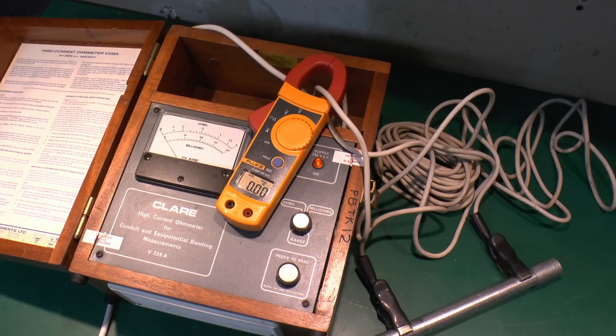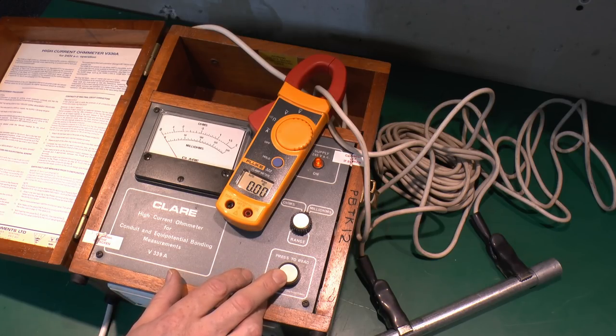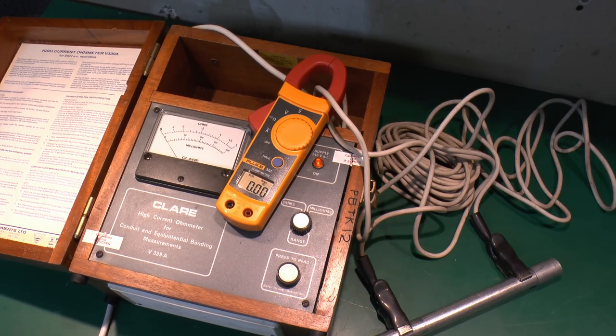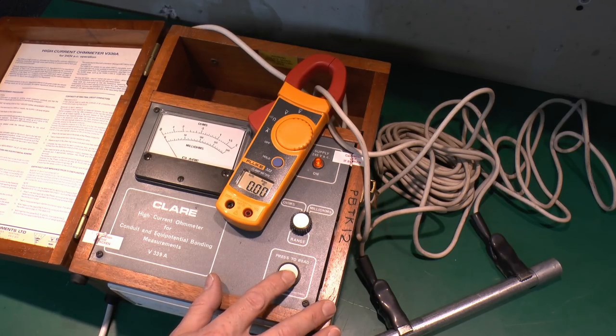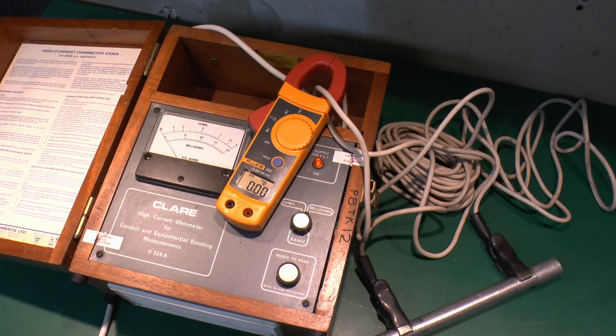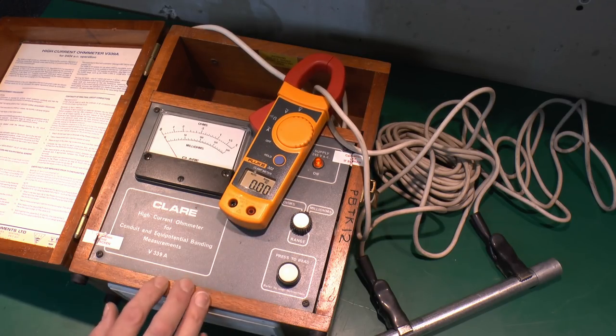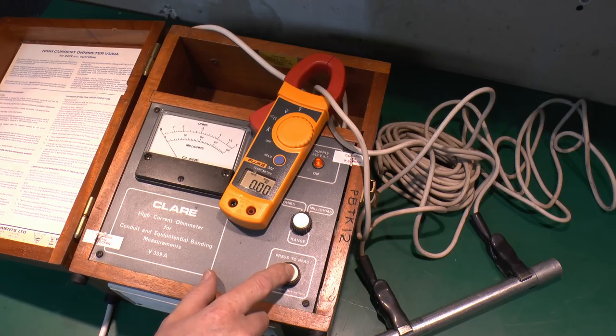Now one thing this does have, because the current it uses is so large, this actually has a thermal cutout inside, so if you hold the button down for an extended time, something inside will heat up and then it will just cut off the thing. So the idea here is you don't apply the test for an extended time, you press the button, read the reading here, and then that's pretty much the test complete. It's certainly not intended to apply the current for a long period of time, and so it does have that thermal cutout inside.